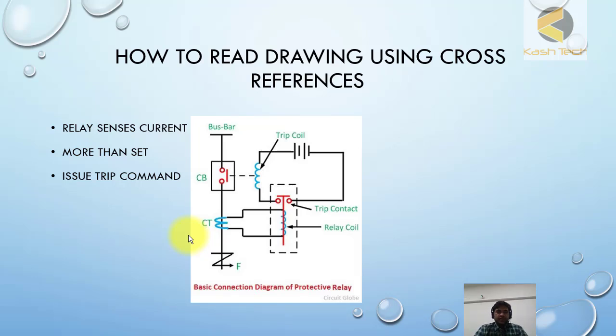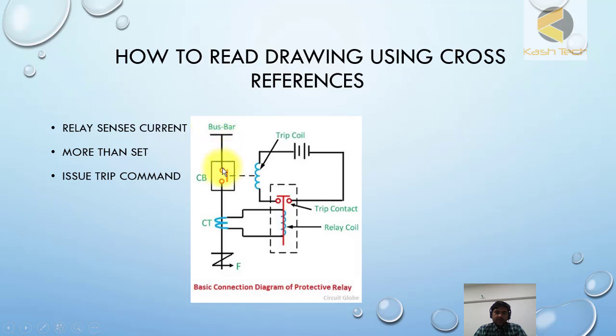For your understanding, I have drawn a very simple tripping circuit diagram. This is not what you will see in actual schematics — I will show you that later — but for understanding the concept this is a very good drawing. Here you can see the circuit breaker named CB, the trip coil, the bus bar, and through the circuit breaker it is feeding a load. This is the CT, which is a current transformer. Just understand that it reduces the current so that the relay can measure it easily.